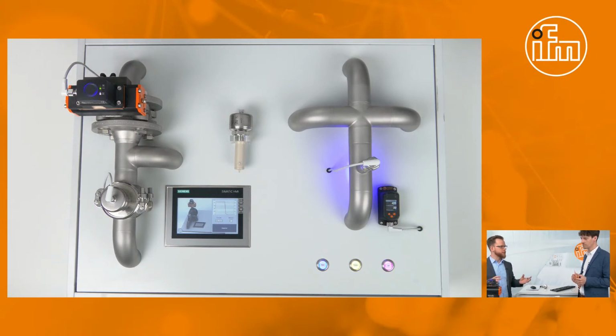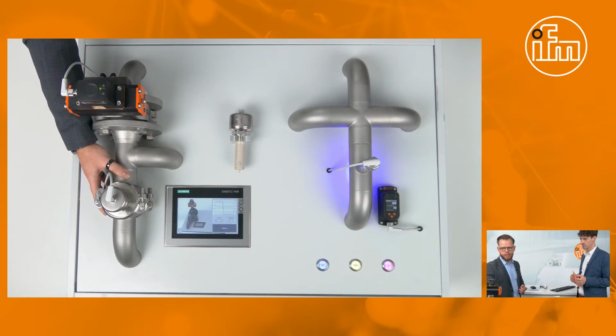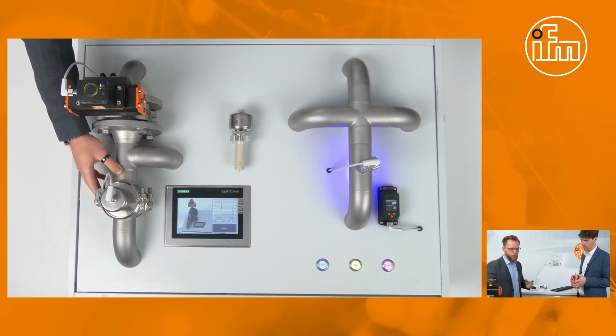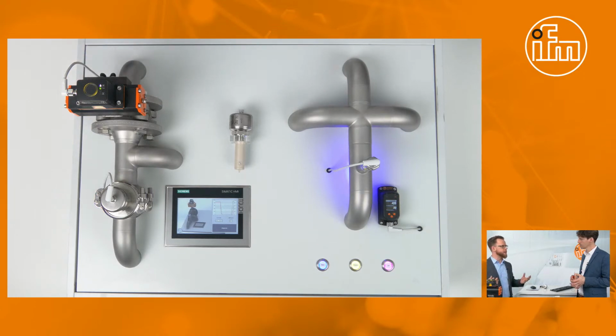What really is the difference is the process connection or the insertion depth. You can see on the right side that the sensor is installed into a Varivent line pot. So when you have, for example, a DN40 pipe, or even up to 2 inches with DN50, DN60, you have to think about the tip of the sensor—because it's a 1-inch process connection, you will fill up the whole pipe and have a huge pressure loss.